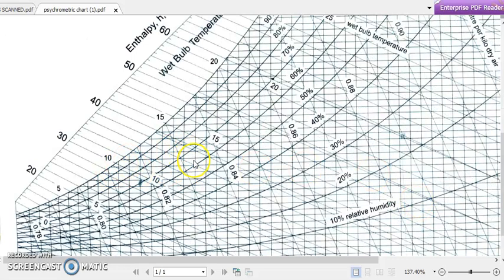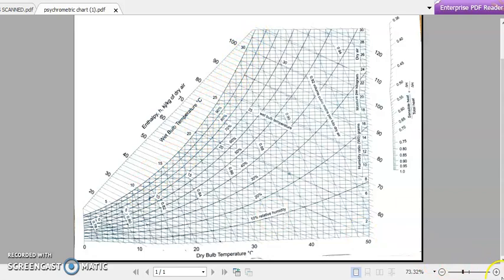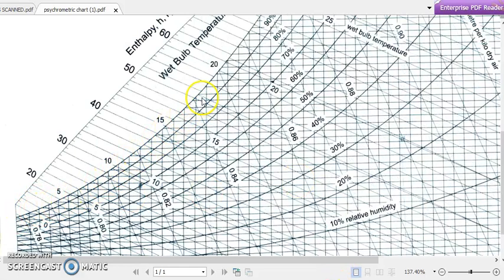The curve on the leftmost part of the chart is the saturation liquid line, representing 100 percent relative humidity. There are also various relative humidity curves — 90 percent, 80 percent, 70 percent, 60 percent, 50 percent, down to about 20 percent. The markings of 5, 10, 15, 20 on the saturation line represent dew point temperatures.